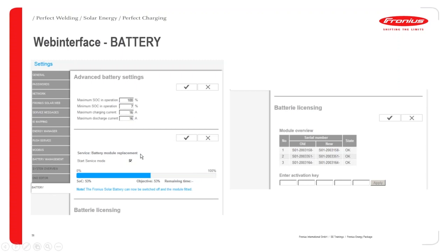Then you've got the Battery tab here. If you want to increase, for example, your minimum state of charge in operation or your charging current, I don't see any reason why anyone would want to change that. A maximum of 16 amps is set here anyway, but if you did want to change it, you can. For example, with minimum state of charge in operation, let's say mid-year you actually want to have the backup function, then you can set that a bit higher so you can always ensure that you've got a bit of power left in the battery if you do go into backup mode.